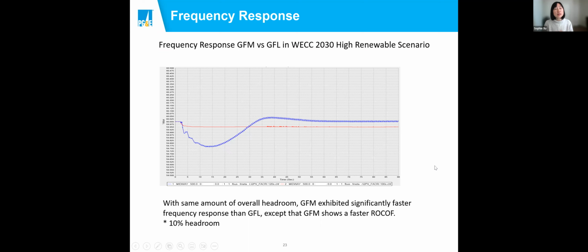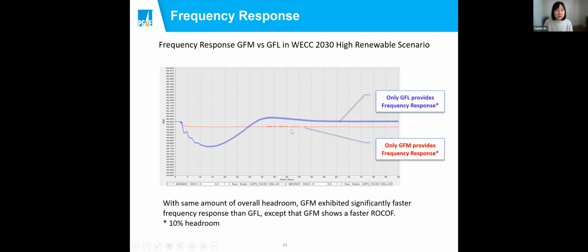And the last thing tested is the frequency response. I did a test on a 10-year-out scenario in the WECC system with a high renewable scenario. The blue and the red are the frequency responses from either all grid following inverters or all grid forming inverters. The red is the grid forming inverter, and the blue line is the result of the grid following inverter. And obviously, the grid forming inverter provides much faster and more effective frequency response compared to the grid following inverter.